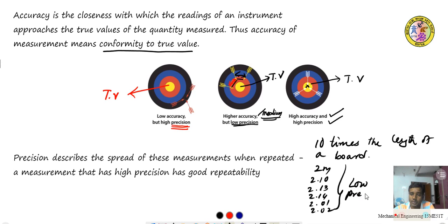If the same board is measured as 2, 2, 2, 2, 2.01, 2.001 each time, that means it has high precision. If every time I measure, the same readings appear, that is called precision. Maybe this reading is not true or near the true value, but the instrument is still a precision instrument.